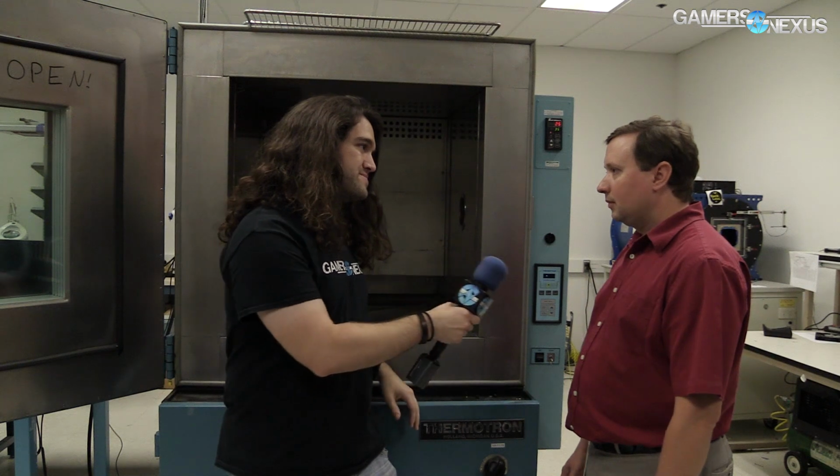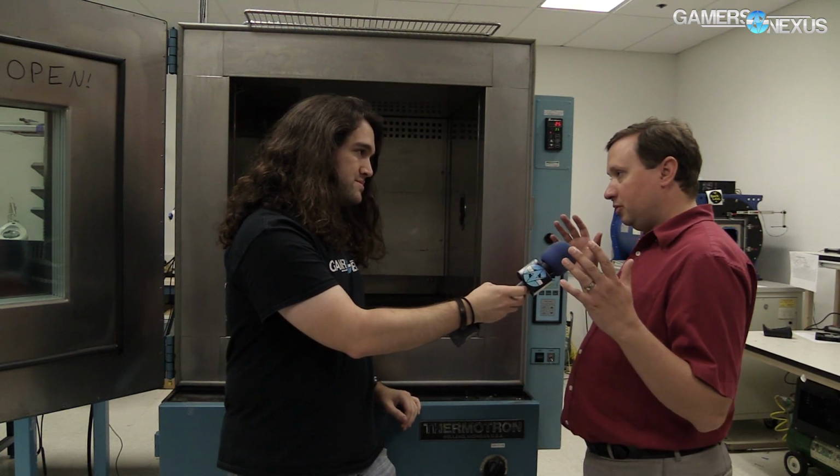So in this room, which you'll see some of in a moment, there's a wind tunnel for fan testing, a thermal chamber, and a Chroma setup for power supply testing. With this, let's talk about the very basics of a thermal chamber. We've already said why you would want one in previous content, but what are some of the different types of chambers available, like humidity, temperature control? Right, okay, so basically a thermal chamber is a heater or a refrigerator in a highly insulated box.